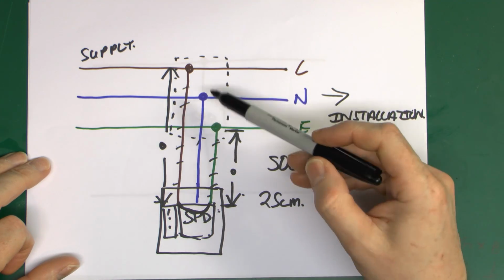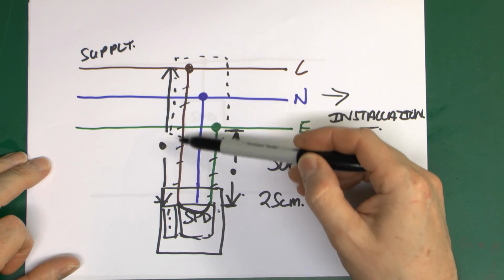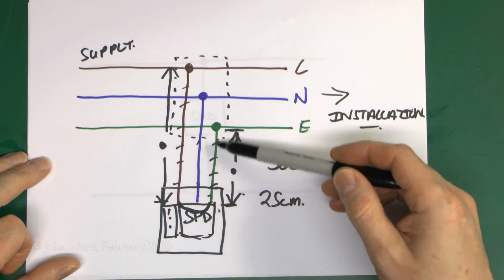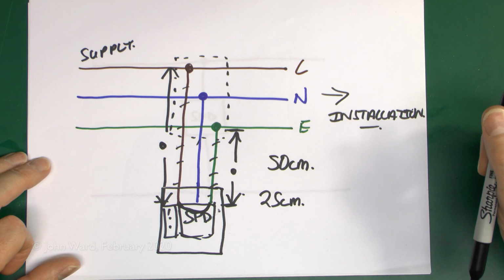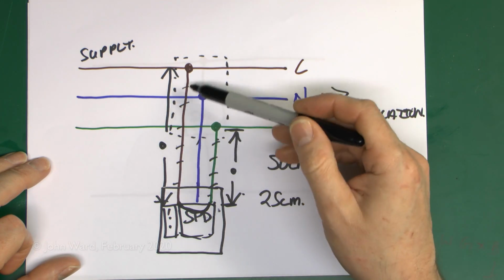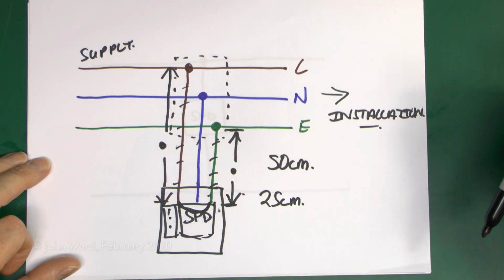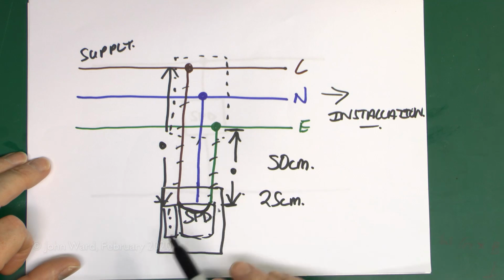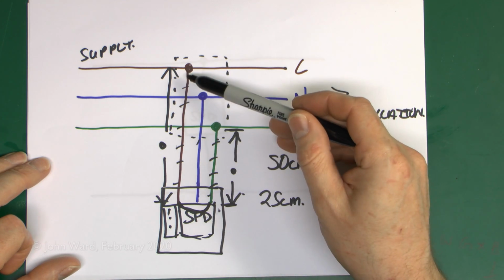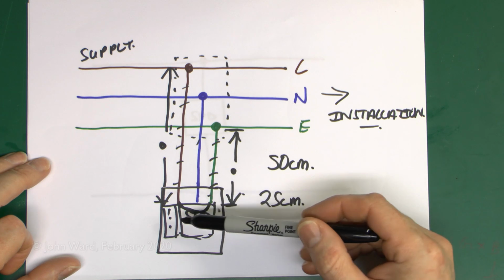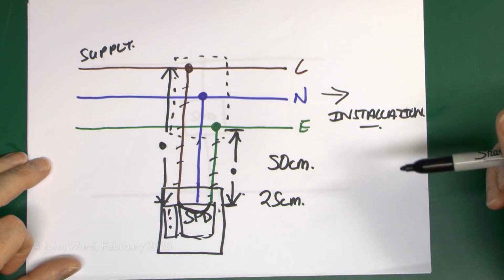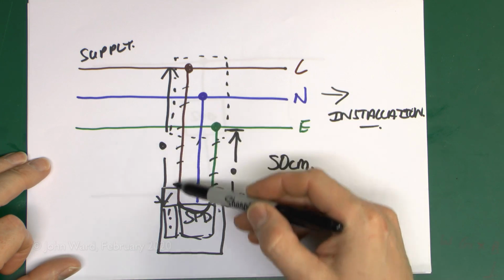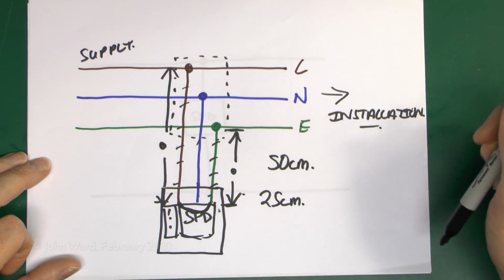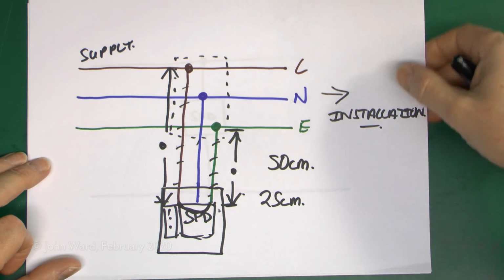Now the reason these lengths are absolutely critical is to do with inductance, and it's actually the inductance of the individual wires themselves. So basically this one here, and either the neutral or the earth, depending on where the current is actually flowing. Now of course a wire, just a straight piece of wire, does have inductance, but it's incredibly tiny. So in normal circuits, it's really not something you would consider because it's incredibly small. But I'll just redraw this here. So we've got basically the line conductor coming through to the surge protection device, and then say the neutral going back. So say the surge was between the line and neutral. So it's the line conductor here, surge protection device, and then the neutral going back. So three things basically in series there.